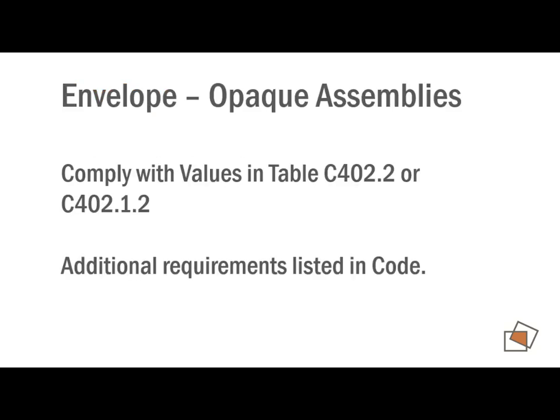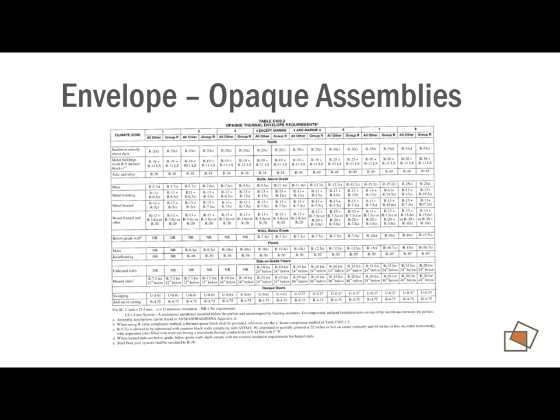So looking first at opaque assemblies, those of you that have designed this are used to this table here, where it's dictating to us based on your climate zone and your construction type, you have certain insulation requirements. For example, we're in this column here, climate zone 4, and this chart is talking about your above grade walls. It says here that for a metal frame wall, you come over here, you have to have R13 insulation and I think a 7.5 continuous insulation. So this prescribes all the R values. You can see the roof R values and your floor R values, things like that.